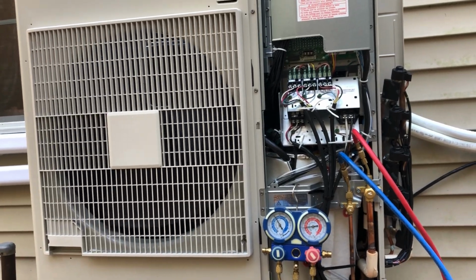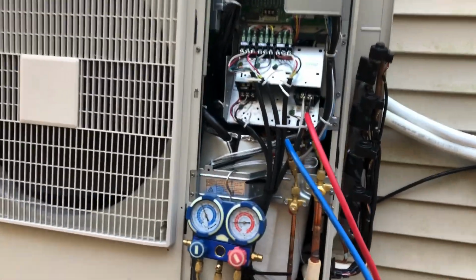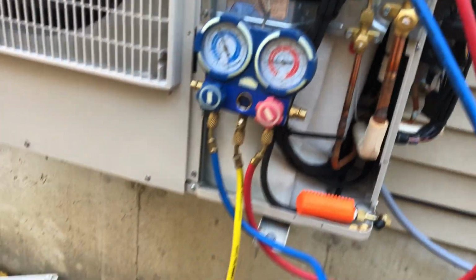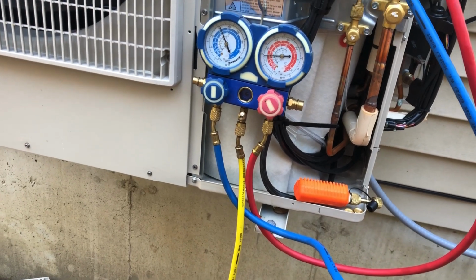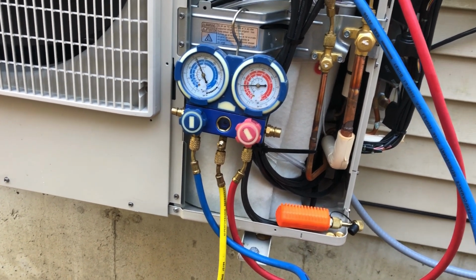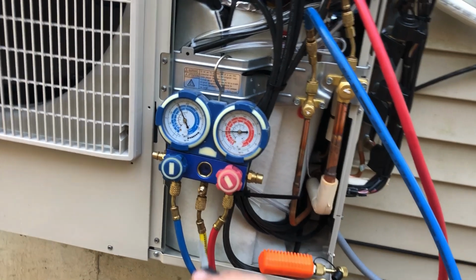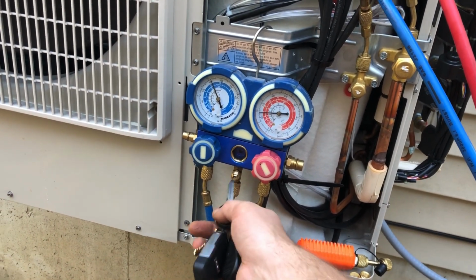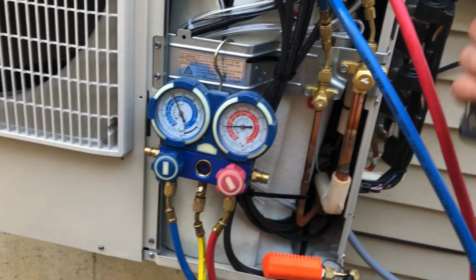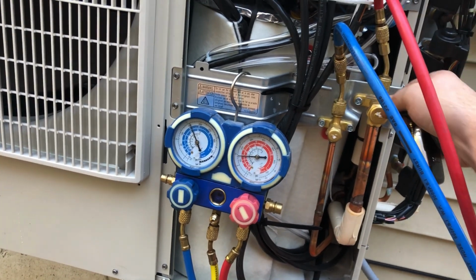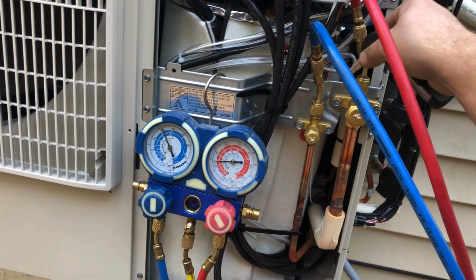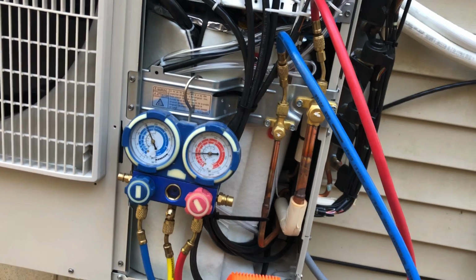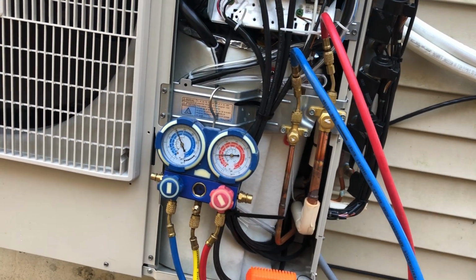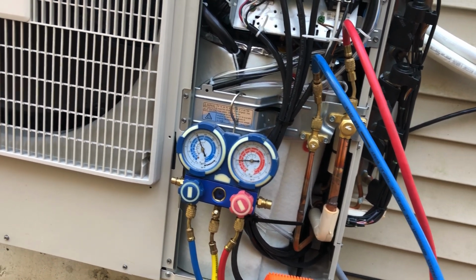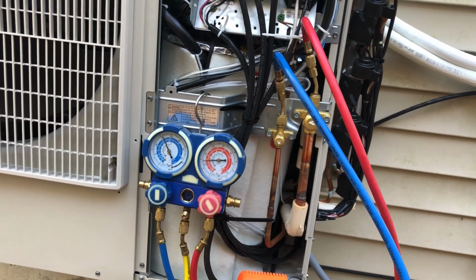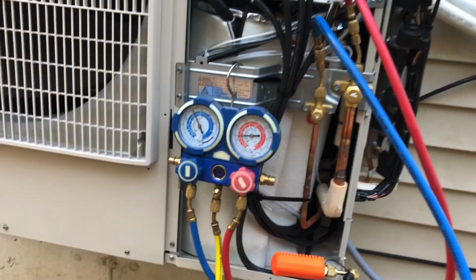So now I'm going to disconnect it. Once disconnected, you need to purge all the air, all the nitrogen, out of the system, and then we'll hook up the vacuum and start the vacuum process. You can purge it by pushing here and opening the valves, or disconnect these on the high and low side and push down on the Schrader valve. You just need to make sure all that nitrogen is bled out before you start vacuuming. That's what I'm going to do now, and then I'll hook up the vacuum pump and come back.